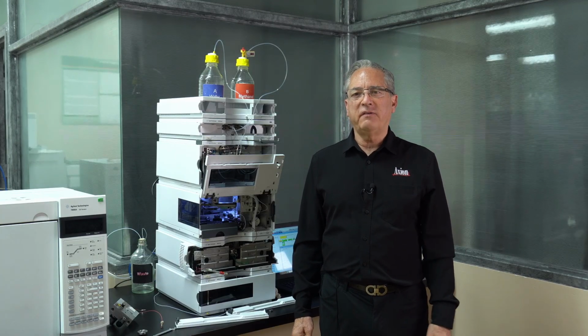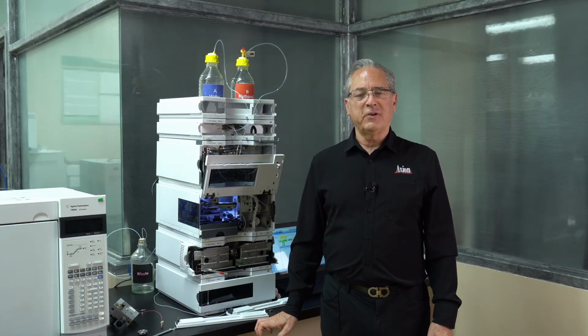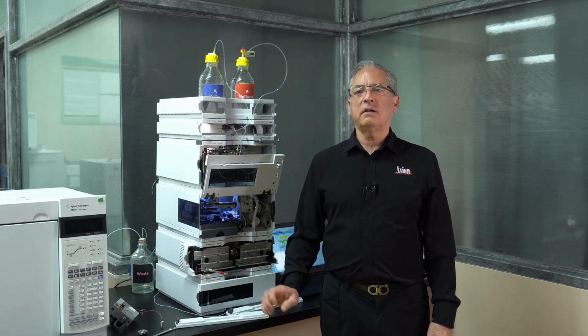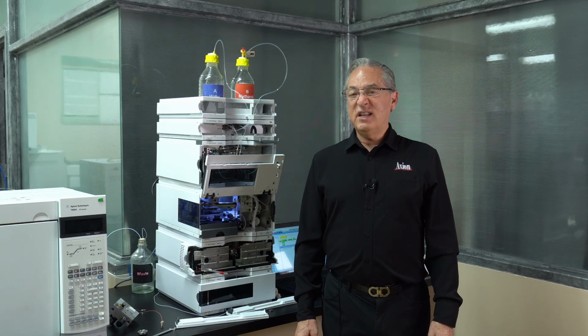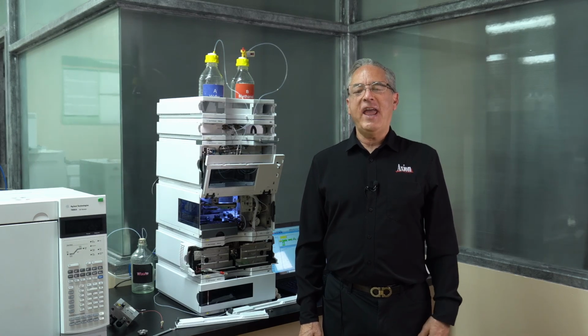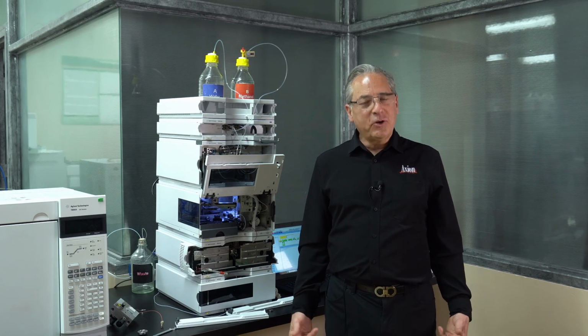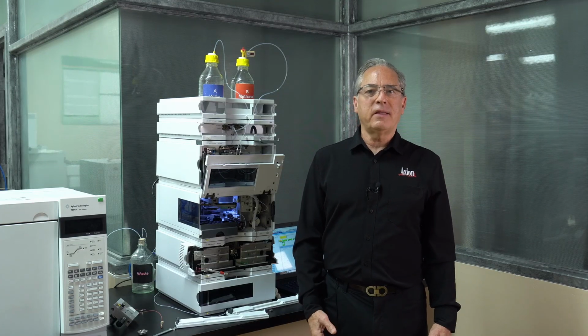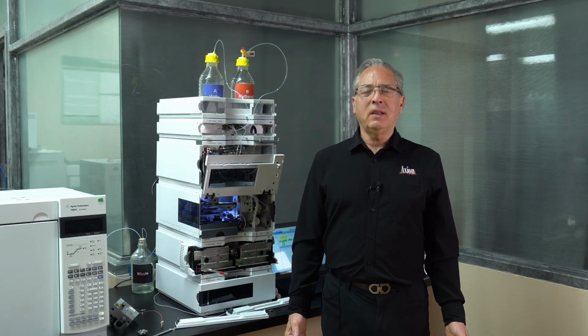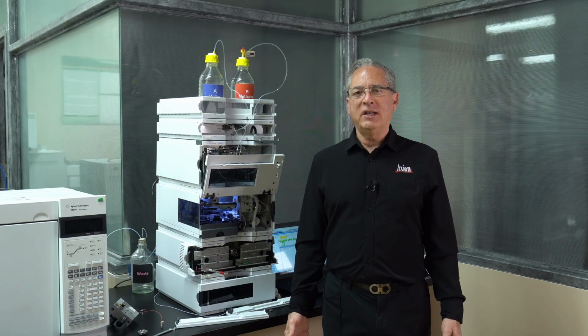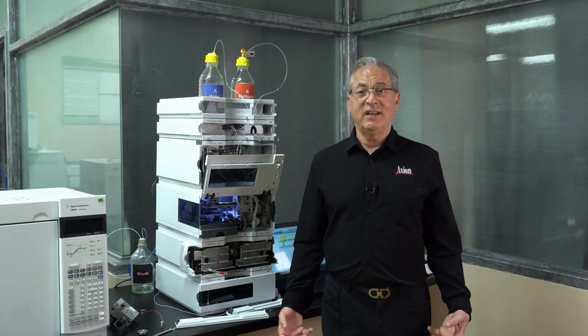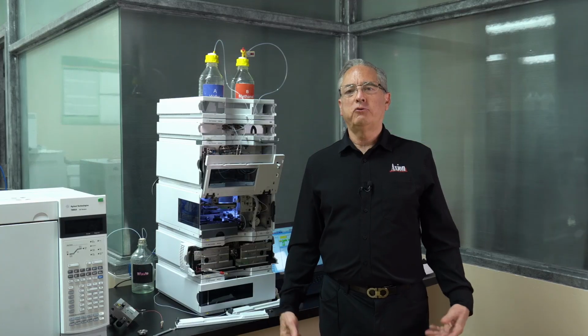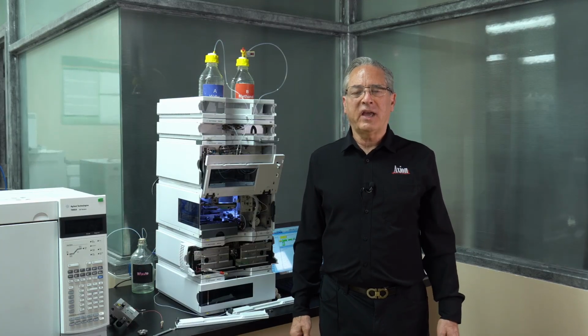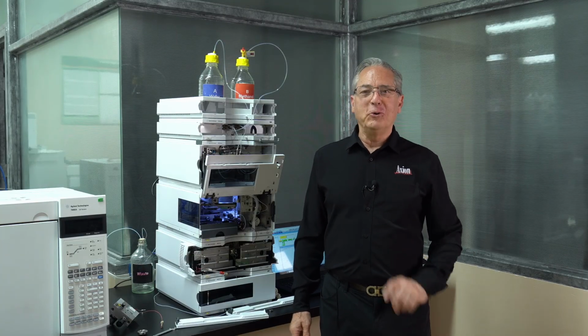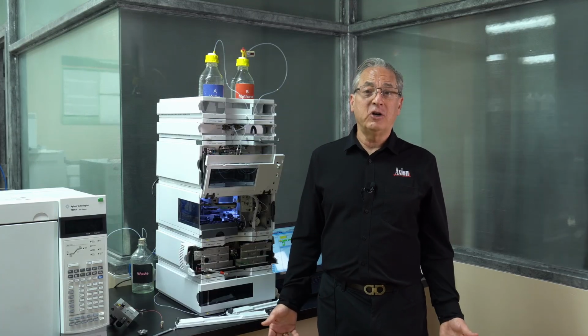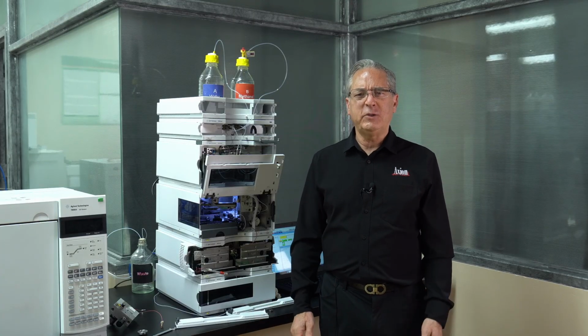So here's a friendly little piece of advice. If your lamp fails to light, it'll say lamp failed to fire, failed to light. That doesn't mean it's dead. Try it again, try it again, and I've found that you'll get it to reignite, and when it does, you'll probably get another couple weeks out of it. So when a light bulb burns out, it's not truly burned out. It just requires more energy to get it to ignite. And what you do is you just try and refire it a couple more times, and eventually it'll catch on. That also tells you it's time to order a new lamp. So we could also check the energy of the lamp in the software, but that's an easy way to look at it.